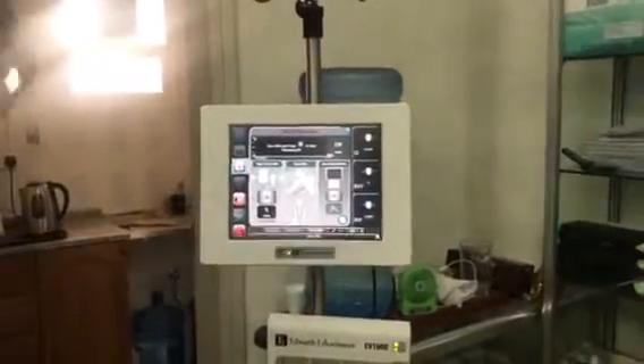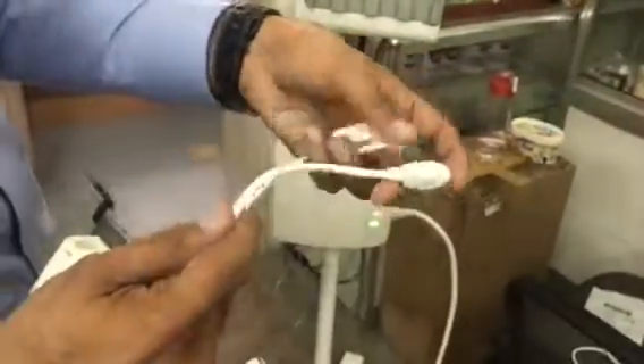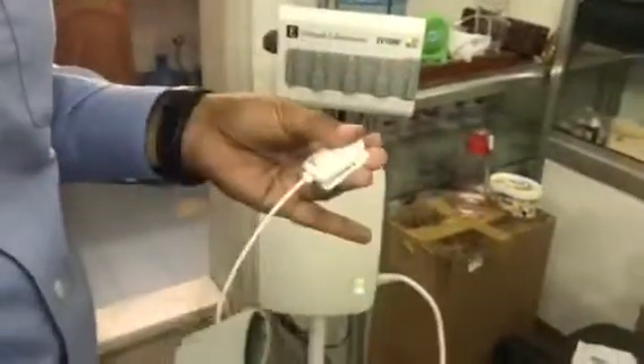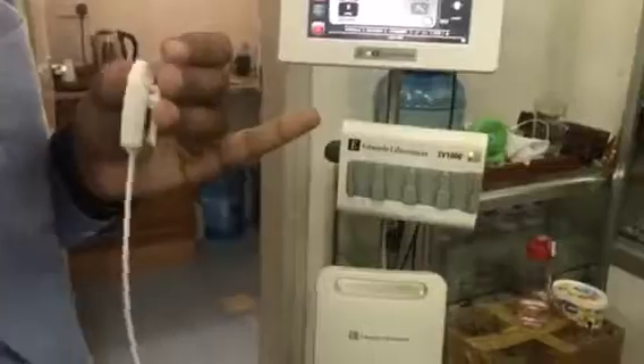Here, as shown, align and zero the HRS. That means this has to be in line with this piece of the device. So this is the heart reference system. Instead of zeroing a normal transducer, this is how zeroing is done in the non-invasive. Once this is done, you have to connect the finger cuff first.